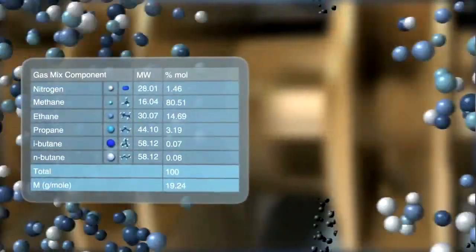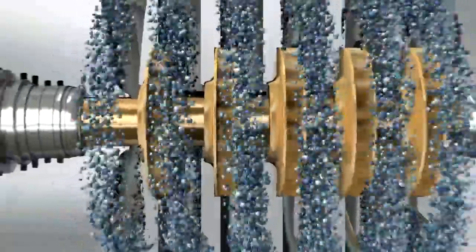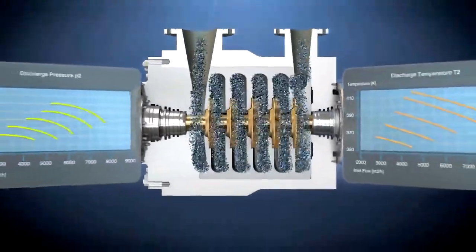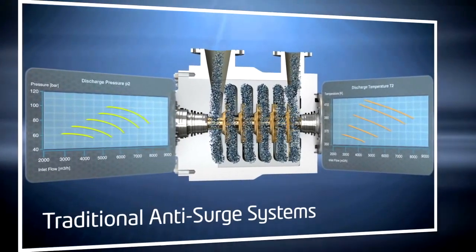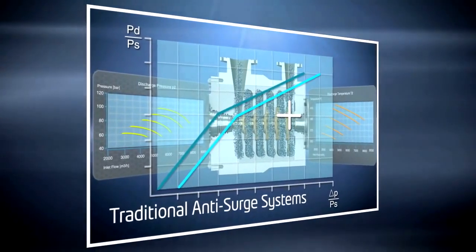Limited because it does not forecast the consequent change of the compressor behavior when it works out of its reference conditions. These systems base every evaluation necessary for the protection from surge on an approximate relation among some main operative parameters, a relation that is considered fixed and invariable.